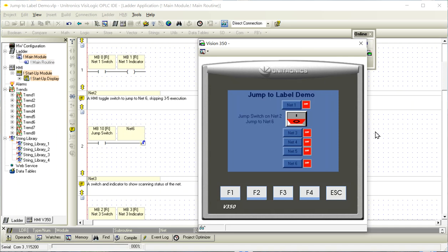Safety wise, they don't like putting that code in a PLC. They like that being done on something that isn't running code with a condition that may stop that safety function from occurring. But they have implemented master control resets in PLC ladder logic.